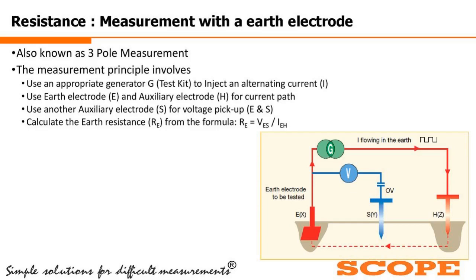Yeah. So, resistance measurement with the earth electrode. Now here we are also coming to what is known as the three-pole measurement. The measurement principle involves the use of an appropriate generator G, or the test kit, to inject an alternating current. Use the earth electrode E and auxiliary electrode H for the current path.